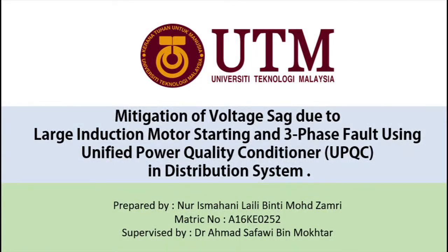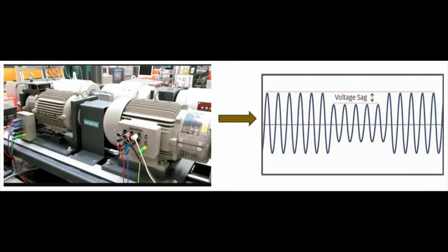I am Nur Ismahan Laili binti Muhammad Zamri, a final year student supervised by Dr. Ahmad Safawi, and I will present on the topic of mitigation of voltage sag due to large induction motor starting and three-phase fault using UPQC in distribution system. Voltage sag is a condition when the RMS voltage falls within 10% to 90% of its original voltage for a duration of half a cycle to 1 minute.